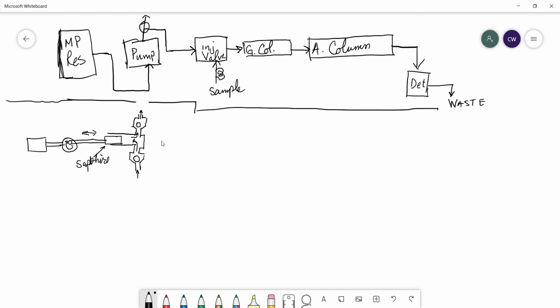Okay? Now, as you can imagine, this can cause some serious pulsing in our fluid flow, right? Because it's only every forward stroke that we're getting any pressure, right? And so most pumps will have a pulse dampener built into them. Okay, and that's just a chamber that takes the eluent and it allows it to be pressurized, and then it maintains it as a constant pressure source. So you can kind of think of it like a capacitor in an electronic circuit, right? It's building up pressure and then it's holding it there constantly, so that during the reverse stroke the pressure does not drop. All right. Okay. So pump requirements.